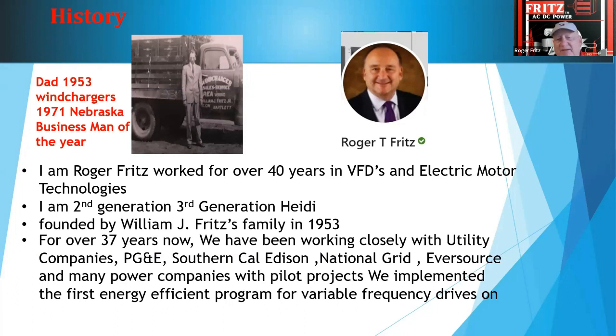And then a little bit by myself, I spent about 37 years working around the utility companies, all the way from the West Coast to the East Coast. I spent about 25 years in the Boston area, working a lot with National Grid, Eversource. I was doing a lot of pilot installations when VFDs were first being developed and applied to applications. So a lot of my experience has actually been hands-on. Finding out what does happen when you put a large number of drives in, that you've got to be aware of noise and harmonics and information that a lot of people don't necessarily want to talk about.